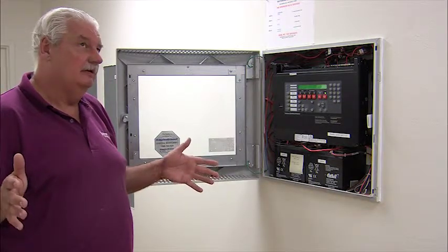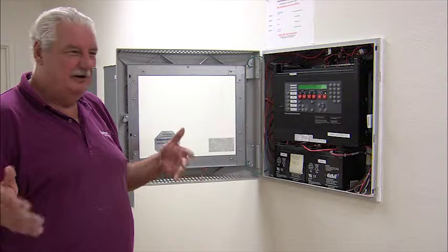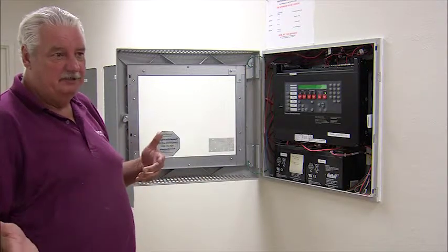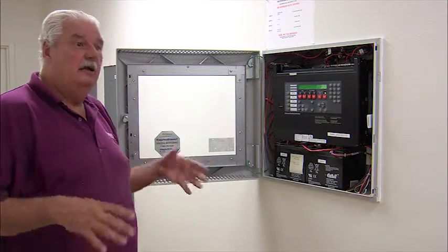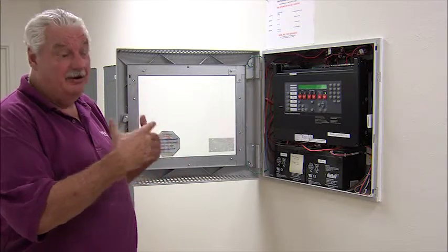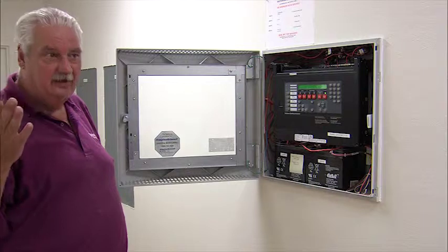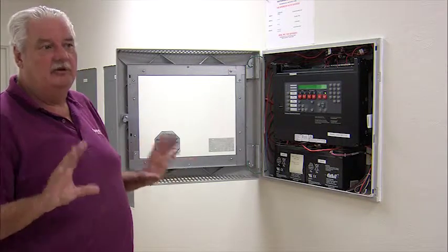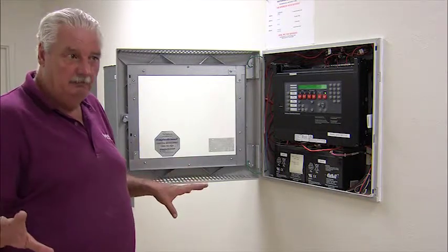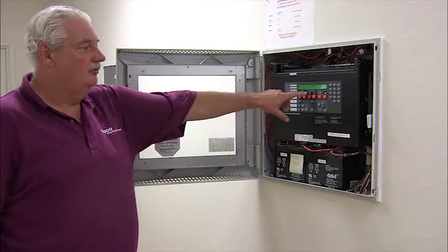Generally that'll happen in the winter after your air conditioning has been run all summer. If the filters haven't been changed, the first time the heat goes on, it may burn the dust, and there may be dust that even the filters won't stop that gets on the coils. It'll burn that off. It may activate the duct detector. The duct detectors do not sound the building alarm. All they'll do is put a supervisory on here.